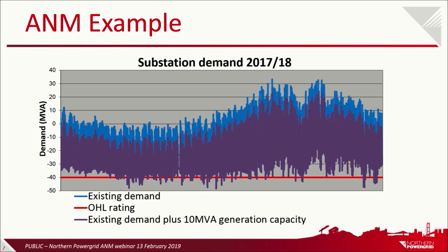So just moving on. Theoretically, if we had a request for another 10 MVA connection of generation capacity onto this overhead line, we would effectively increase the power flow in the exporting direction on this overhead line. So that's basically a shift of that load profile on the overhead line down by another 10 MVA. And you can see there on the graph that at numerous points throughout the year, we're actually exceeding the rating of that overhead line, upwards to nearly 50 MVA on a line that's rated at 40 MVA. So what the ANM scheme does is control that new generation connection, if you like.